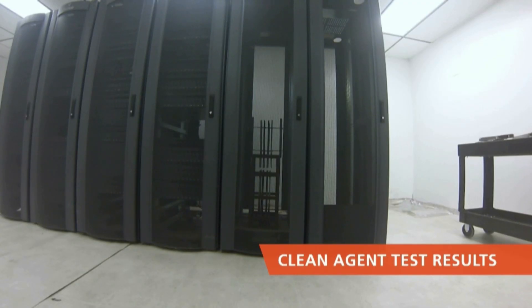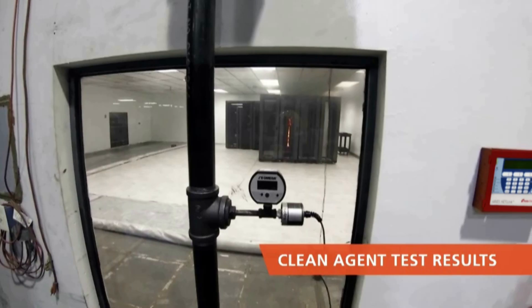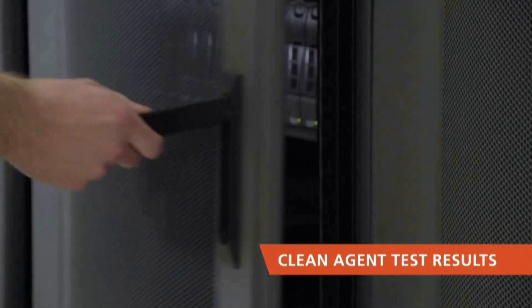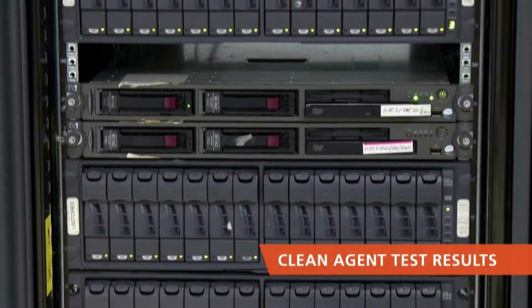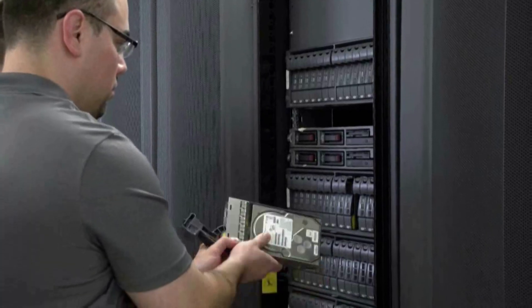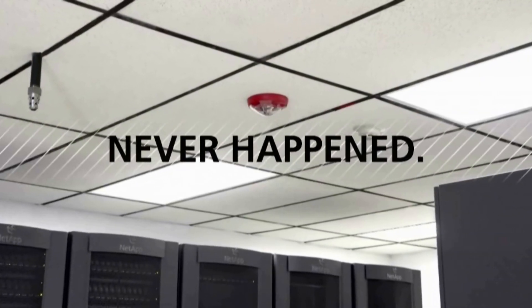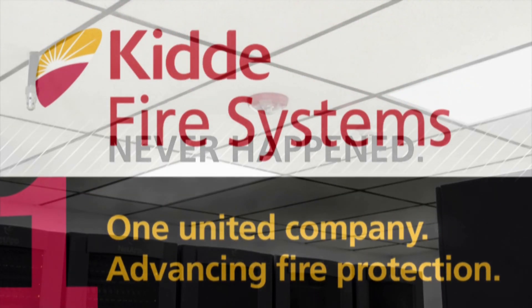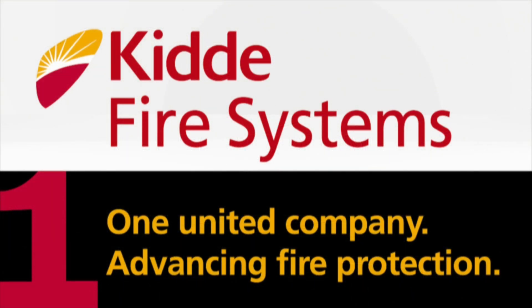The results of the Kidde clean agent system test are dramatically different. Even though the cabinet temperature reached 230 degrees Fahrenheit before the agent discharged, the room and servers show virtually no sign of damage. From the perspective of IT operations and data security, it's as if the fire in the data center never happened.